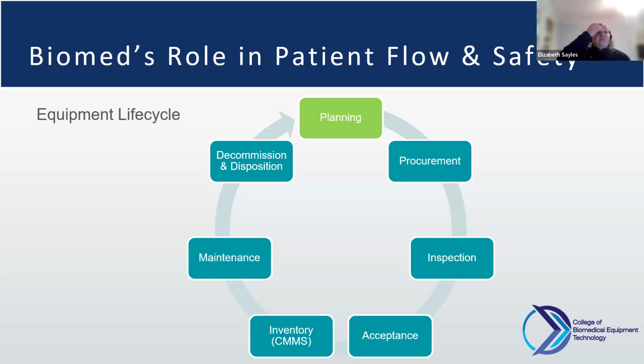So this is the life cycle of equipment, meaning that any device or system that is in a healthcare organization really goes through all of this. And in your department, different devices and systems are going to be in different places within this life cycle. So what I mean by that is, let's say that your healthcare organization has a large amount of infusion pumps that are becoming end of life by the medical device manufacturer. And it was decided by the hospital that they were going to replace them. So you'll be in the department, in that planning phase where you're trying to decide, okay, how are we going to start the process to figure out what we're going to replace our existing infusion pumps with in terms of technology.